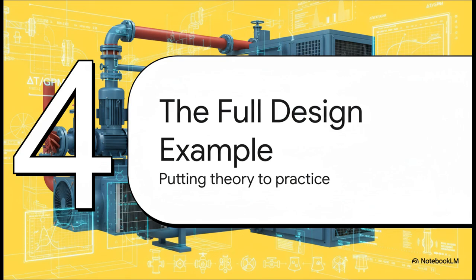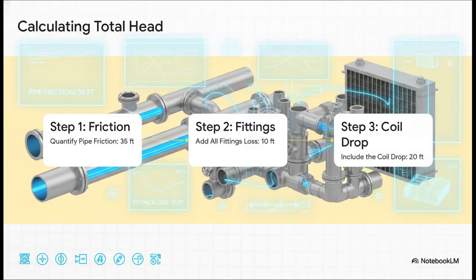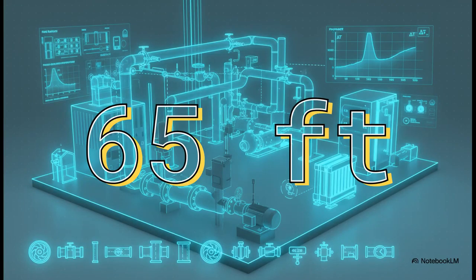Okay, that's enough theory. Let's be honest, the best way to really get this is to just walk through a real example step by step. We're going to take everything we've talked about and put it all together to size a pump for a project right now. First things first, we've got to calculate our total head. So for this example, let's say a detailed analysis tells us our pipe friction adds up to 35 feet of head. All those little elbows and valves, they contribute another 10 feet. And finally, the manufacturer's data for the main cooling coil says we're going to lose 20 feet of pressure pushing water through it. So you add those all up, 35 plus 10 plus 20, and boom, 65 feet.